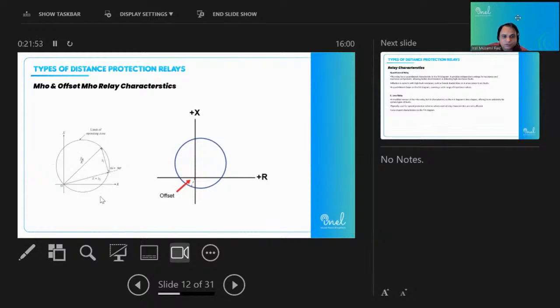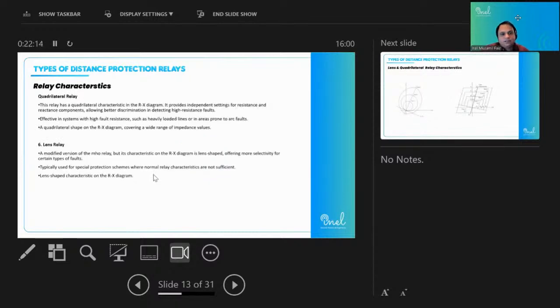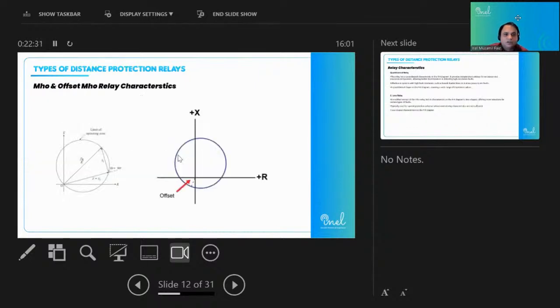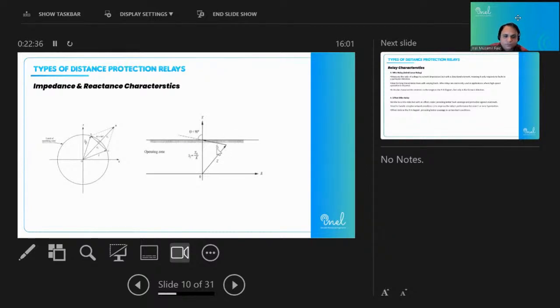Basically, you need to consider this is the mostly used characteristic, like the relays from Siemens, relays from SEL, relays from MiCOM Schneider. These all are using this kind of characteristic for protecting transmission lines. Now there is another one, which is the quadrilateral characteristic, and this type of characteristic has freedom in setting your R values as well as your X values. Like in this reactance relay, the resistance reach was infinite. It was going on this side and also on this side, and it was non-directional in nature because it was detecting faults on both sides of the transmission line, on the right side and also on the left side.